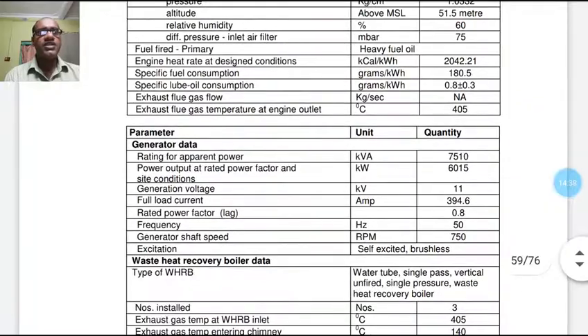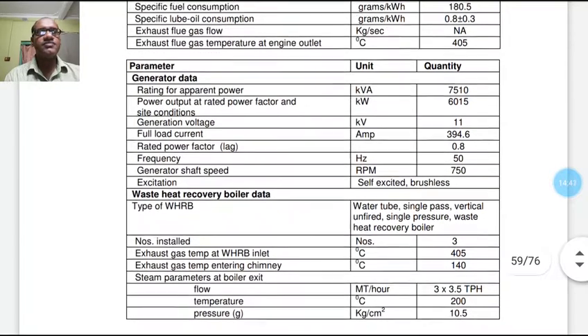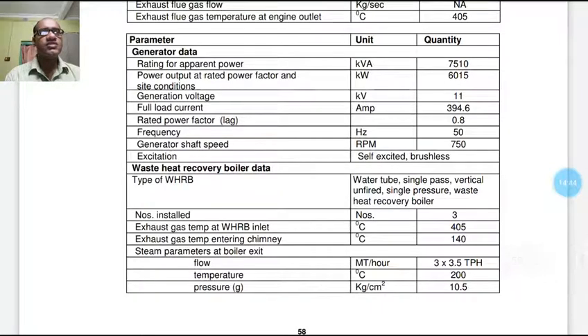Now the generator data rating is given: 7510 kilovolt ampere. Power output is 6015 kilowatt. Generation voltage 11 kilovolt. Full load current 394.6 ampere. Rated power factor 0.8, frequency 50, generator shaft speed 750, and excitation is self-excited, that is brushless.